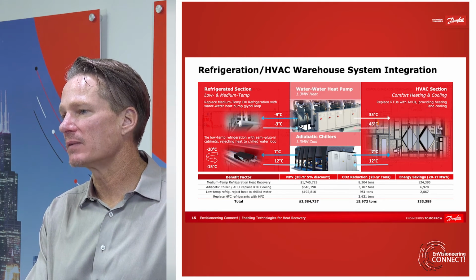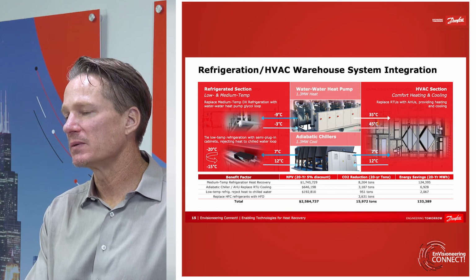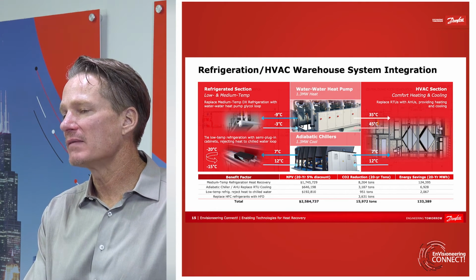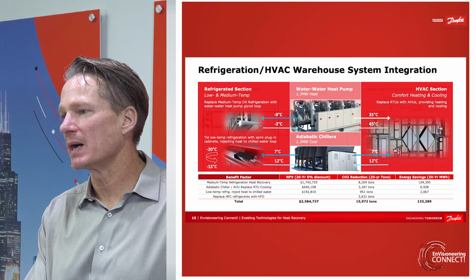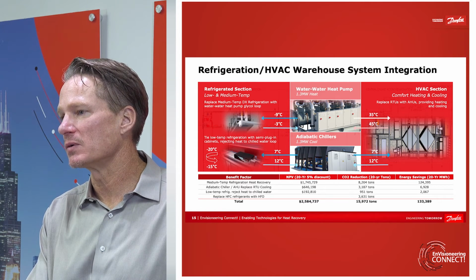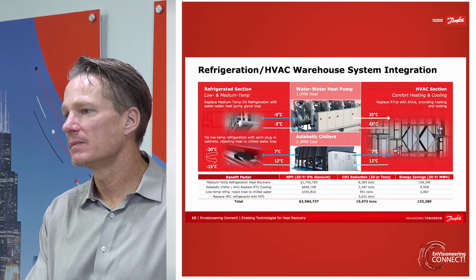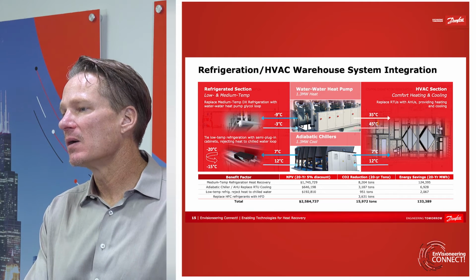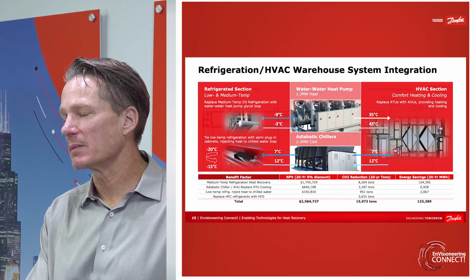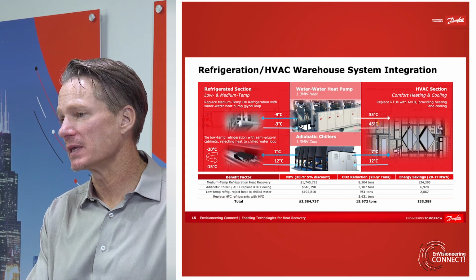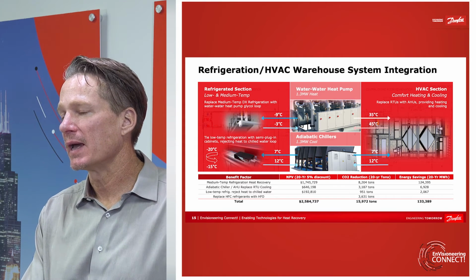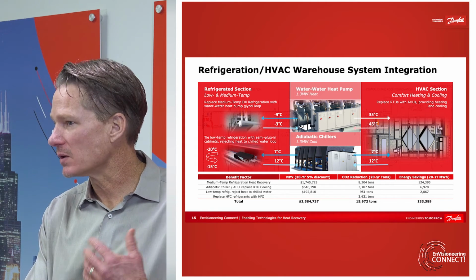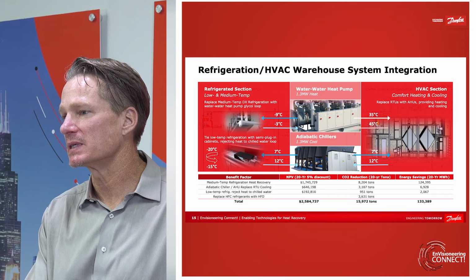So now we're recovering the heat from that medium temperature refrigeration, and then we're also increasing the efficiency of that low temp refrigeration system by rejecting the heat to the comfort cooling chilled water loop. And then at the same time, we're eliminating a significant portion of the HFC refrigerants that they were formerly using and replacing them with HFO, which also increases the decarbonization potential.